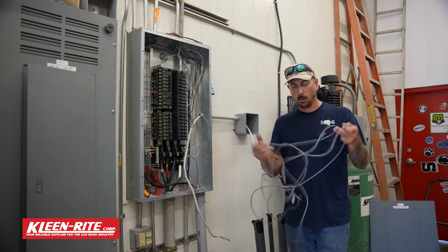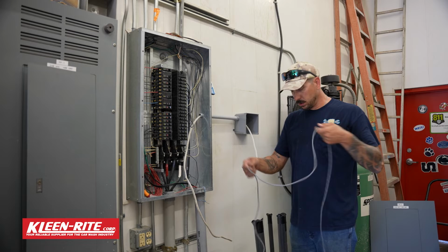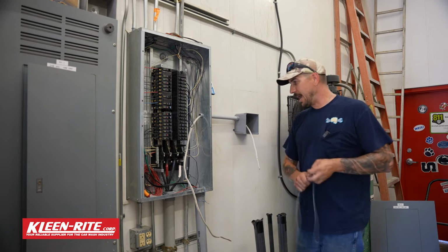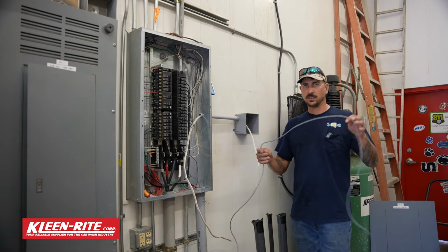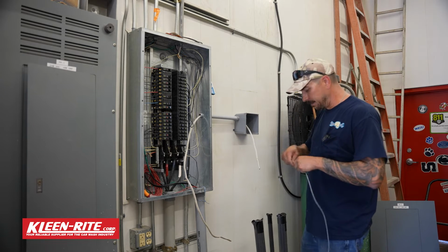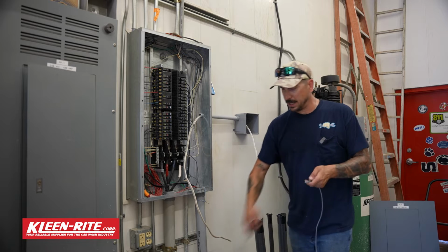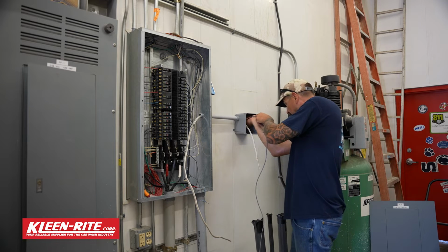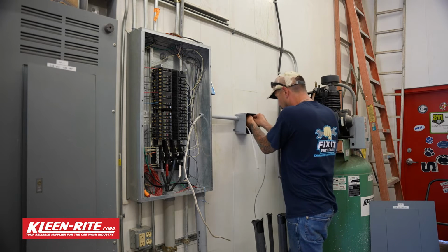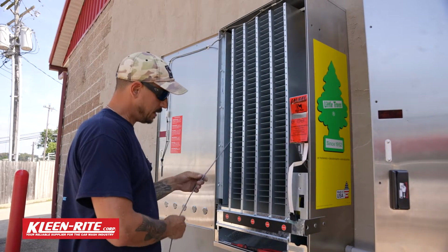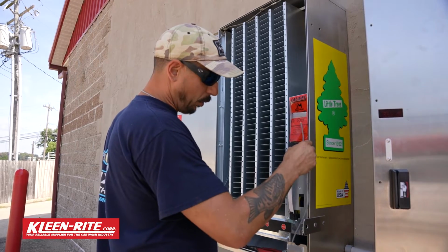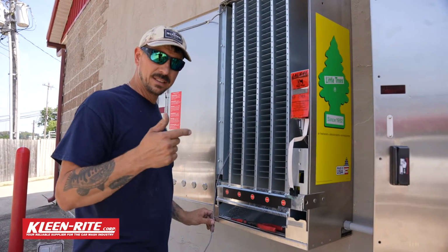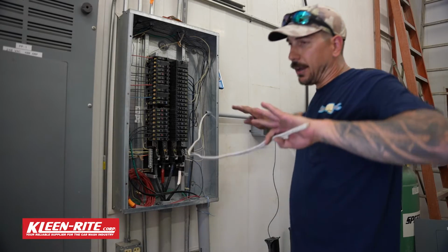And we're actually going to go ahead and push our 24 volt wire through the wall into the vending machine. That way we don't get everything hooked up inside here and then have to try to struggle around that. A trick for pushing wire through a wall or a tight space is to bend it over on itself and then crimp that down a little bit, and that'll give you a nice little pushing nub to be able to force that through the wall. All right, so we got our wire through. I'm going to pull enough that I know I can reach my board, and we're going to head back inside and get that wired up. All right guys, so we got all of the wiring pulled.